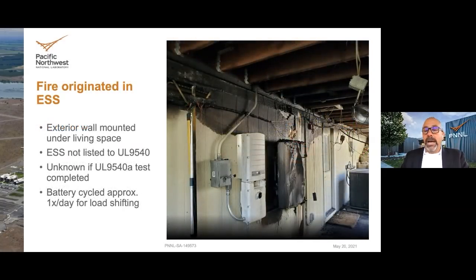This is the location of the battery fire. This particular battery, at the time, was not listed to UL 9540. There's a bit of a problem right now with the versions of 9540 — we're currently on the second edition. The first edition did not require residential batteries to go through the 9540A fire testing that was explained earlier. The second edition, out for about a year now, does require all wall-mounted residential units to go through that fire testing. So it's really a function of which code is adopted and which version is referenced, but nevertheless this is considered a gap in the residential market.